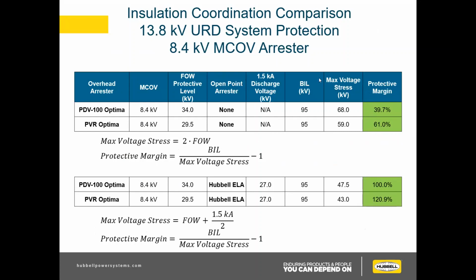Over here, for an 8.4 kV MCOV arrestor, this is without an elbow arrestor. This is comparing your PDV-100 Optima to your PVR Optima. In this case, both of them are fine with a BIL of 95 kV. No problems here. You're well over the 20% recommended, so nothing to worry about. Here, this is with an elbow arrestor. You can see how your protective margin benefits from having an elbow arrestor.